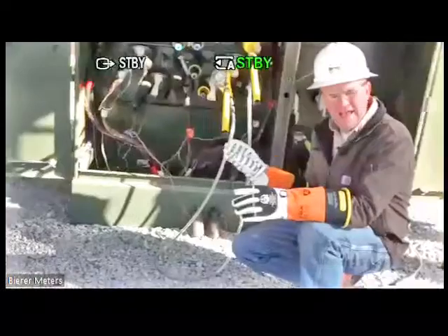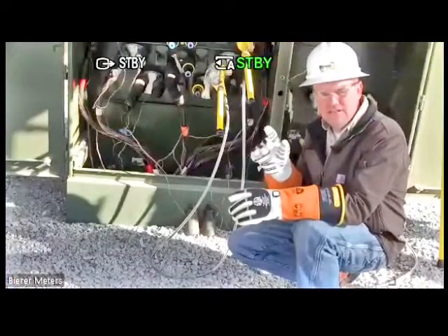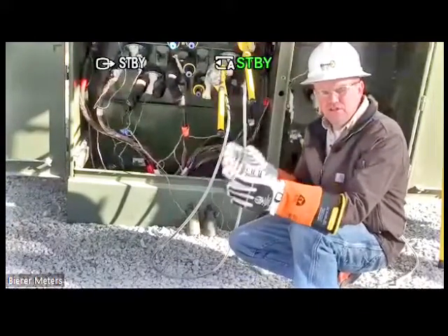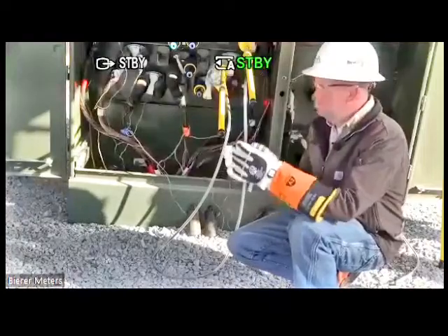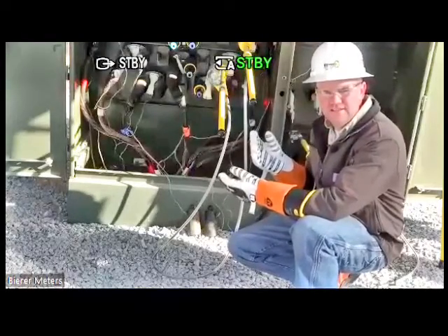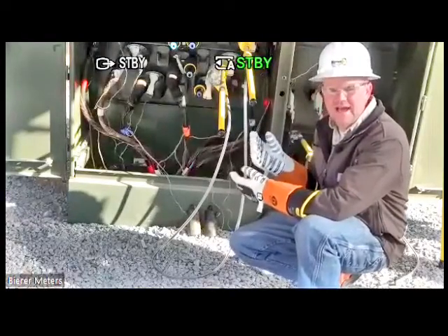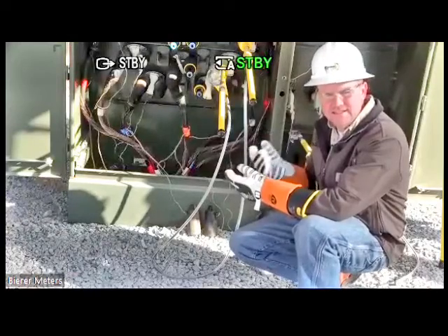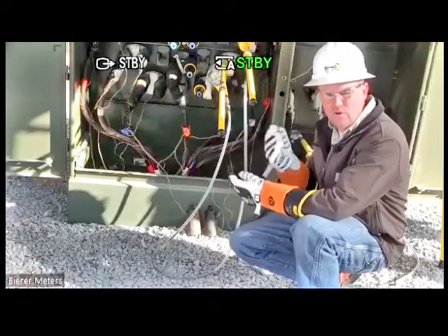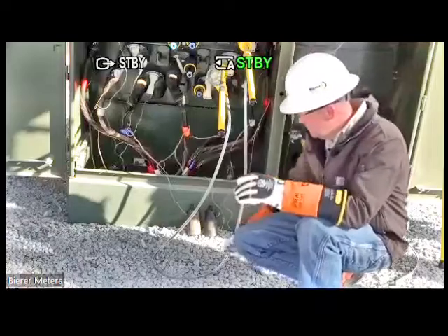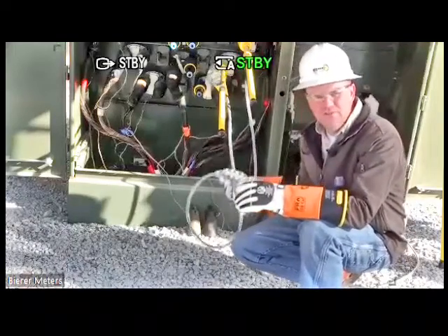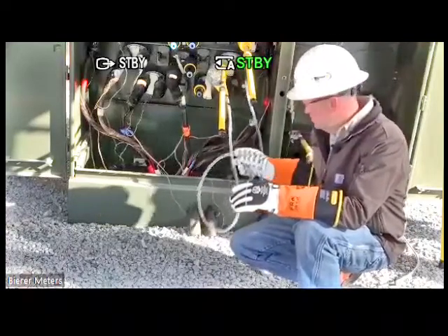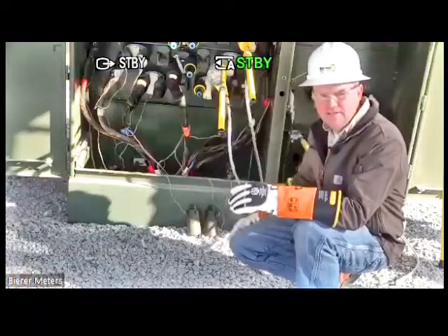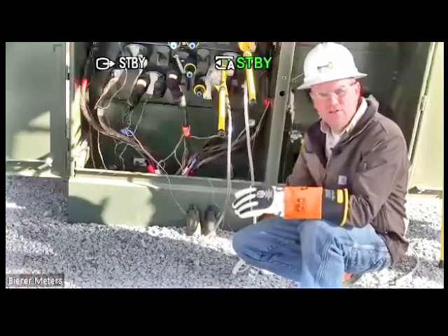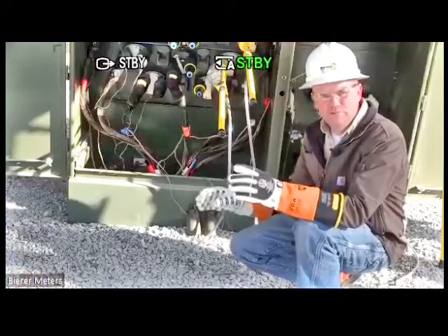So even though these aren't accurate readings because I have that phase sequence adapter in there, you're still concerned with the readings because I want to know which phase is leading what. I want to see which one has the higher reading. But it's consistently going to be accurate as far as telling me which one has the higher reading, regardless of how this cable is laying. Okay, so again, it could touch the cabinet, touch the ground, doesn't matter. Doesn't matter how long this cable is. I can still perform this function.